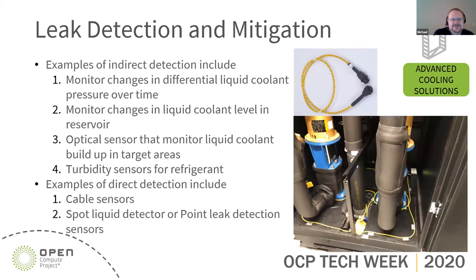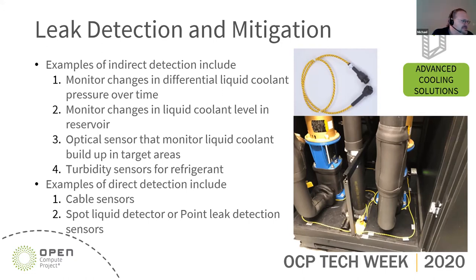There are two forms of detection: indirect and direct. Indirect detection examples include monitoring system pressure — looking at pressure drop for fluid supplied to a whole rack. Also, if there's a reservoir in the CDU or manifold, tracking the fluid level to see if it drops is a definite sign of a leak. Optical sensors or turbidity sensors can detect bubbles in the flow — a sign of air or gas leaking into your system.